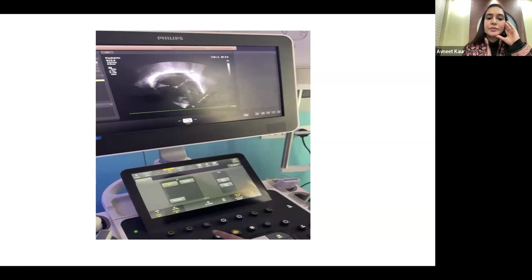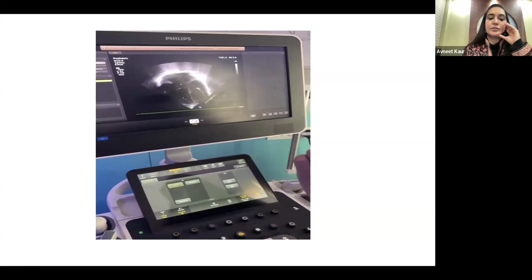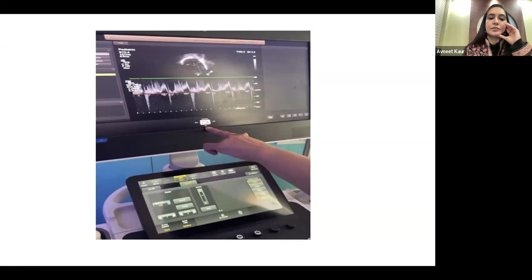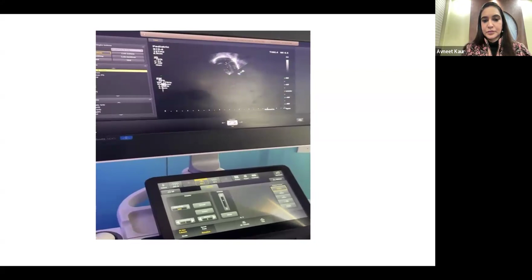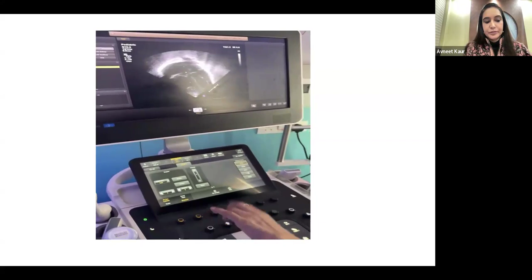And I want to do pulse wave Doppler, and I want to choose the Doppler sample gate. When I press PW, you can see a sign coming up, sample volume, the sample gate volume. So how do I adjust the sample gate volume? I select the sample gate volume size, and I can adjust it to as high as even 15 millimeters, or as small as even 0.5 millimeters. That's how I can adjust my sample volume gate as well.